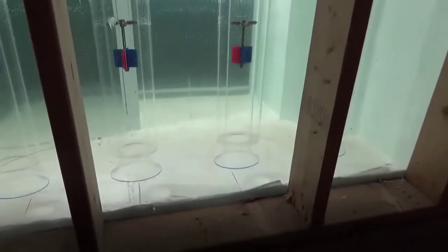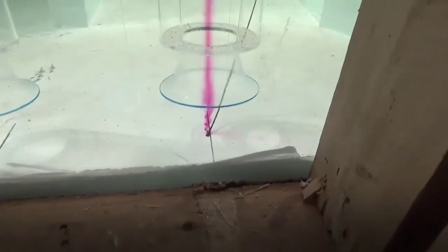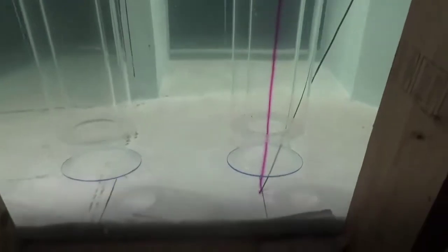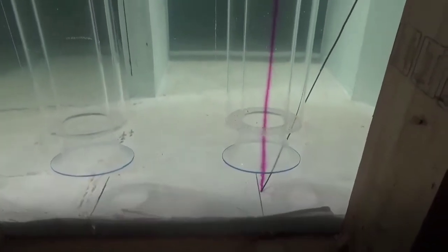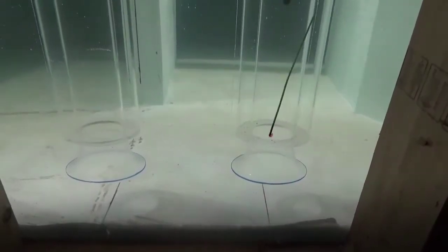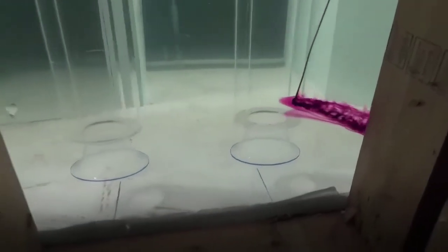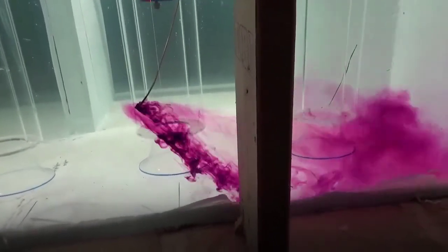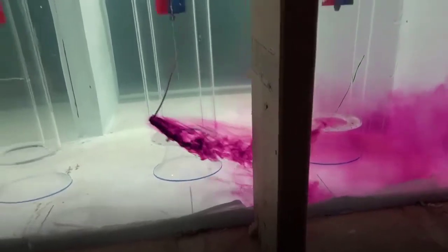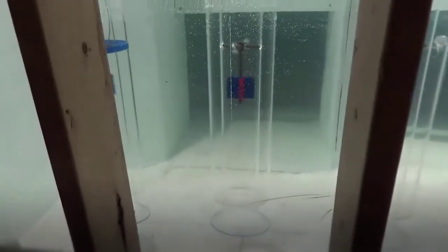So let's go ahead and put a little bit of dye underneath here. Same vortex that you see, very well organized right there. We'll go ahead and put a little dye behind the pump. And you see again that same circulation back here behind that pump. Even with 4 pumps running, it's going all the way over to the sidewall right there. So 4 pumps, 5 pumps, very, very similar.